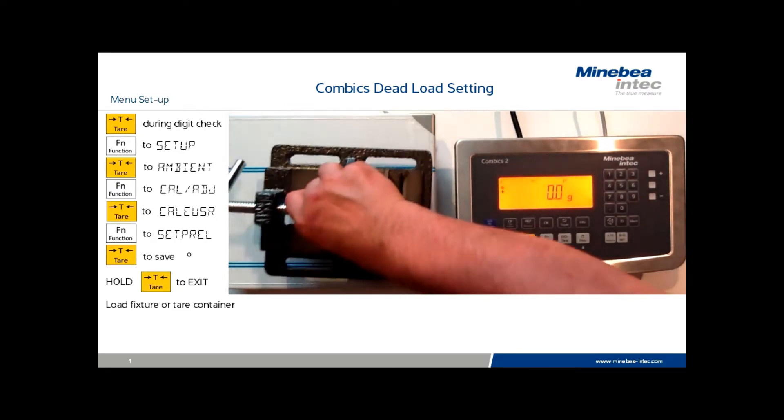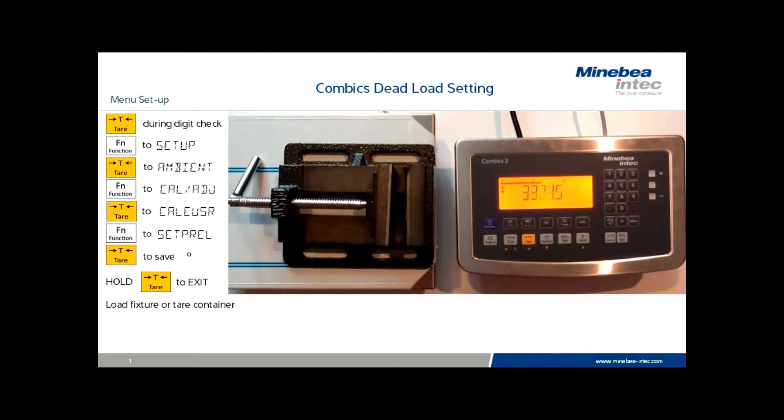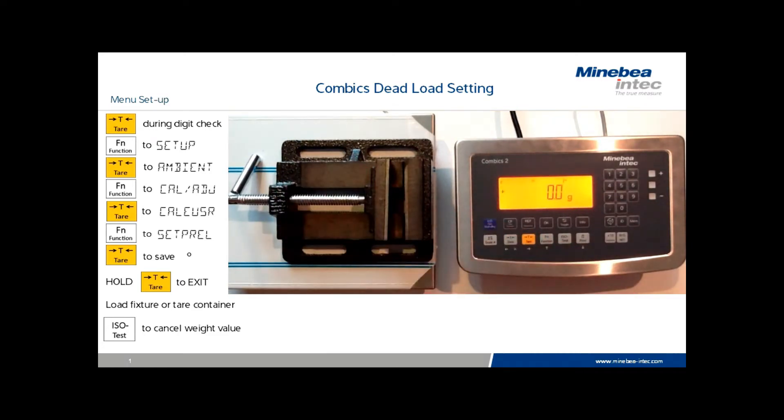Once the scale has stabilized, place your holding fixture on the scale and press the ISO test key, which has now been redefined as a set preload function. The scale will go to zero. If the fixture is removed, the scale will display L, and it will not be possible to tare or zero unless the fixture is in place.